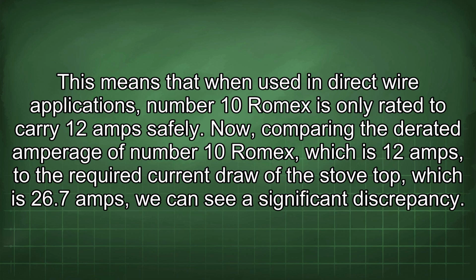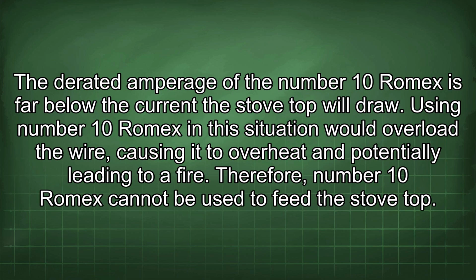Now, comparing the derated amperage of number 10 Romex, which is 12 amps, to the required current draw of the stovetop, which is 26.7 amps, we can see a significant discrepancy. The derated amperage of the number 10 Romex is far below the current the stovetop will draw. Using number 10 Romex in this situation would overload the wire, causing it to overheat and potentially leading to a fire. Therefore, number 10 Romex cannot be used to feed the stovetop.